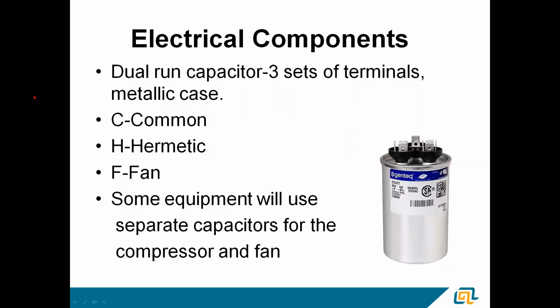Almost all of our equipment has dual run capacitors in it. It's got 3 sets of terminals on it and a metallic case. C is the common wire, so that's power into the capacitor. H is the hermetic or the compressor terminal. F is the fan terminal, of course. Some equipment out there will have separate capacitors for the compressor and the fan, so it'll just be a single run capacitor.